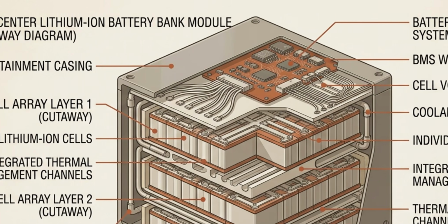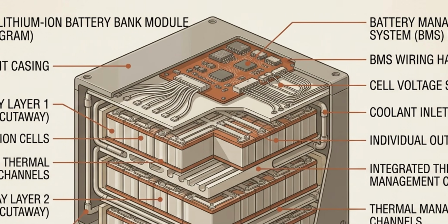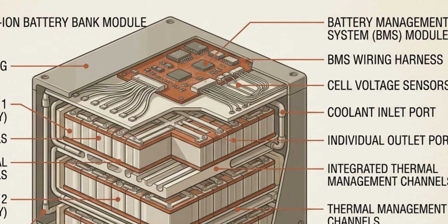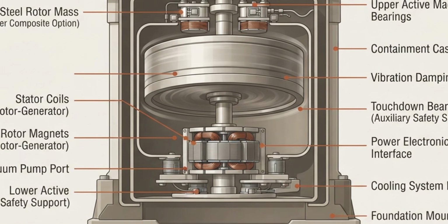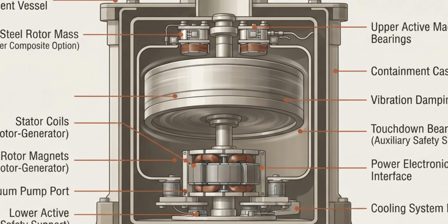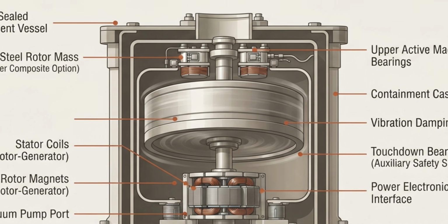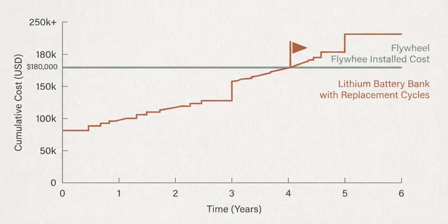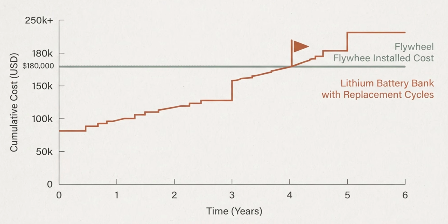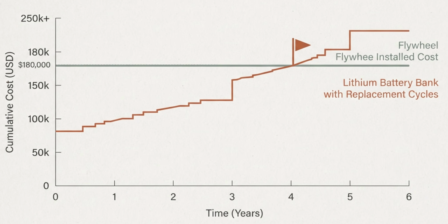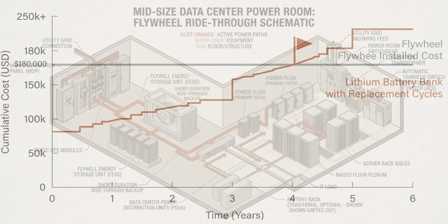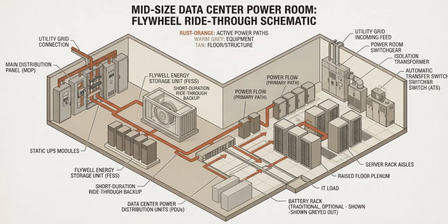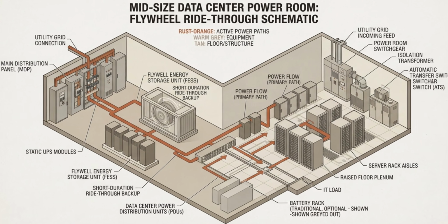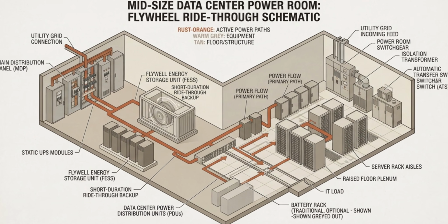Modeling the installed cost for a unit sized to a mid-sized data center puts you right around $180,000, compared to an equivalent lithium buffer bank at roughly $400 per kilowatt hour of short-duration ride-through capacity. The flywheel pays for its premium in avoided battery replacement cycles inside of 6 years, based on the numbers. Not bad for the entry point on this list, but it only gets more interesting from here.